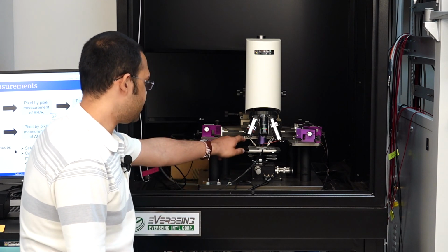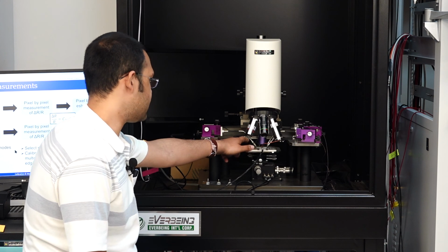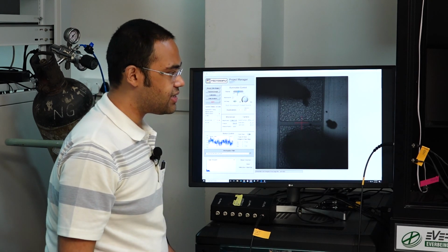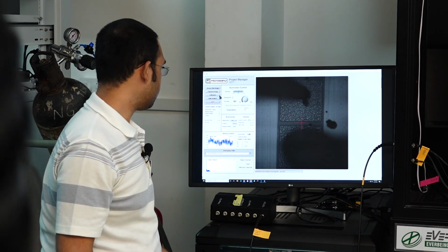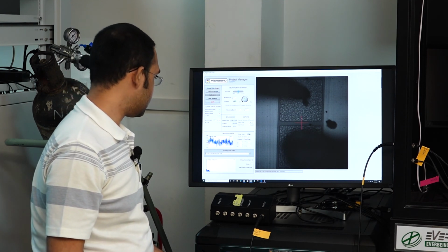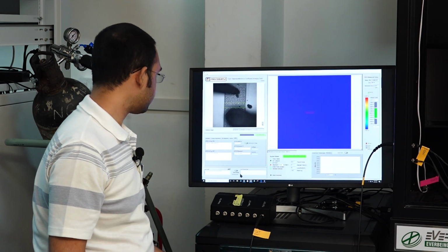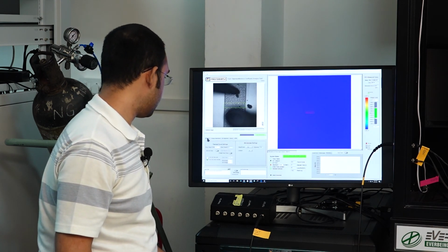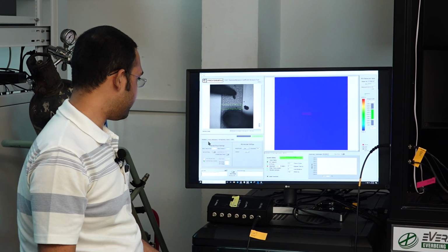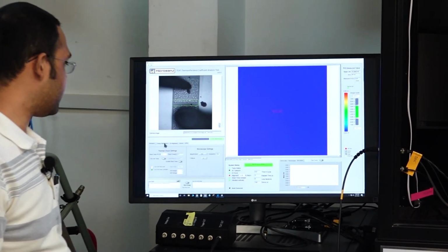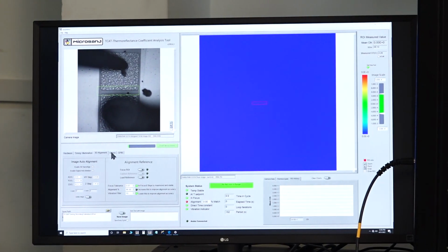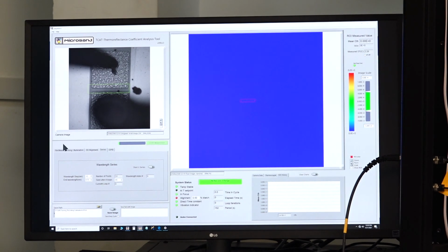As I had mentioned in the previous discussions, the thermocouple, which is probed here, will measure the corresponding change in temperature. So with the setup in place, in the software, in the project manager window, you can see this tab called calibration. So we press this and the calibration window opens up. Here there are multiple sub-tabs present. For example, we have this hardware module, the timing illumination of the LED module, the 3D alignment module, then the wavelength series module and other control modules.